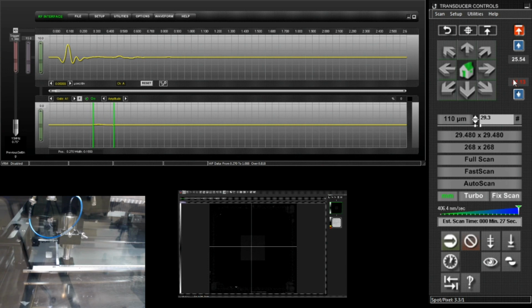So back to the transducer control, and we're using the up and down arrows, and you can see the signal changing amplitude as we drive up and down. So we're looking to maximize that echo, and then it's focused. That's now maximized and now focused. Perfect. Next, the gate position. As we want to image the top surface, we want to put the gate over the top surface echo. That's a bad position. That's a bad position. You want to include the complete waveform of that echo as a good starting point. So that's the focus, the gate.